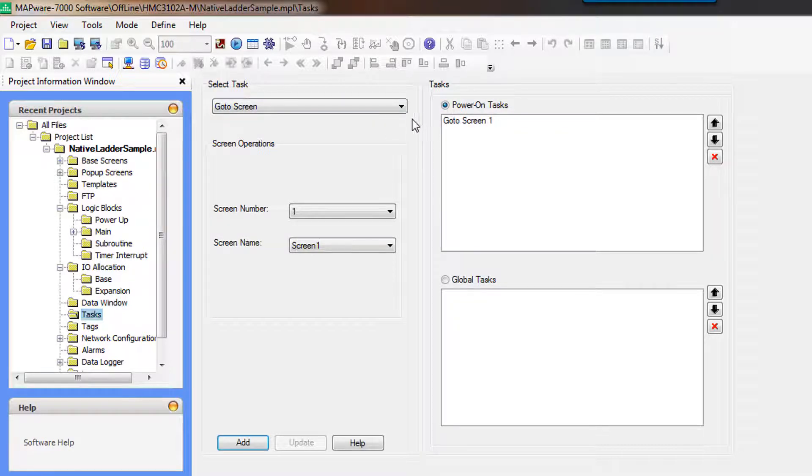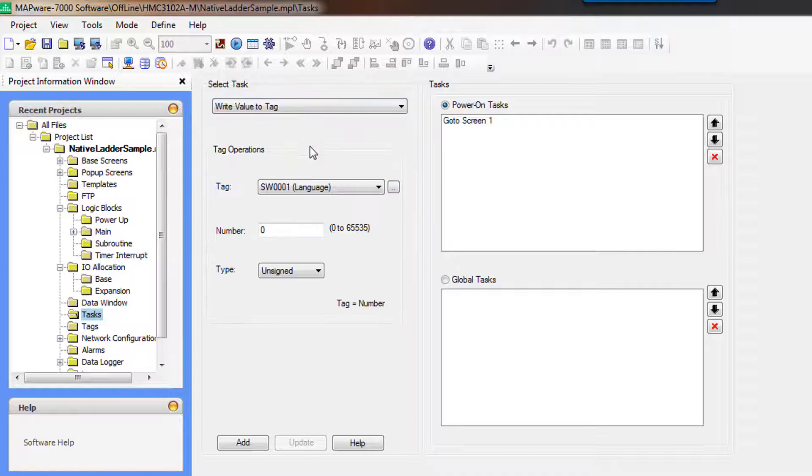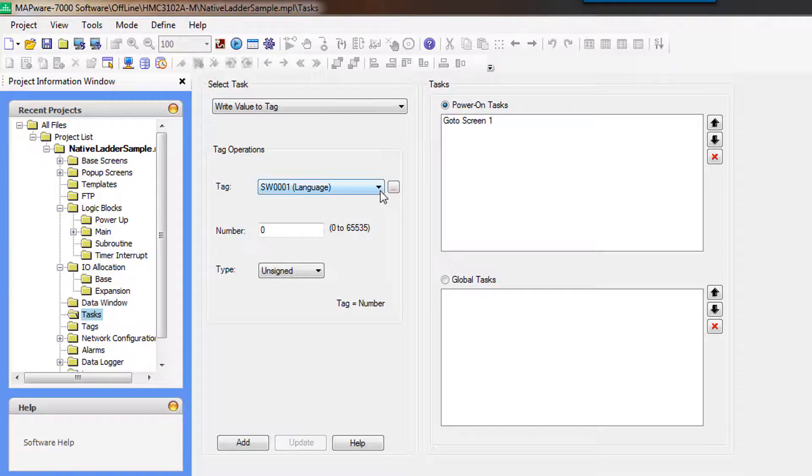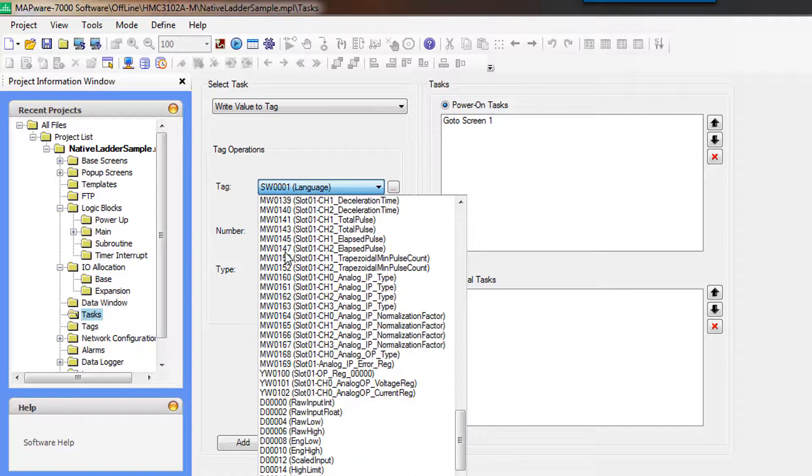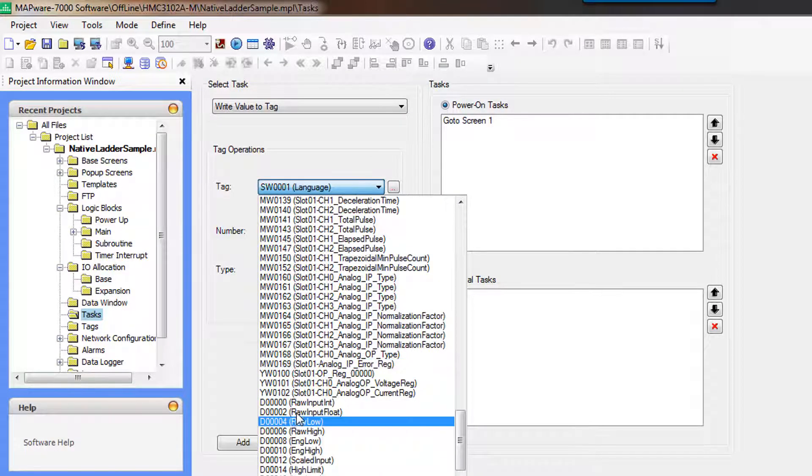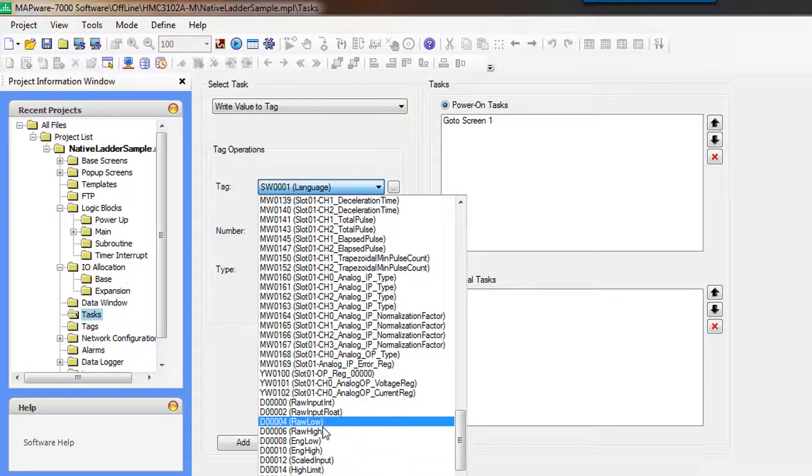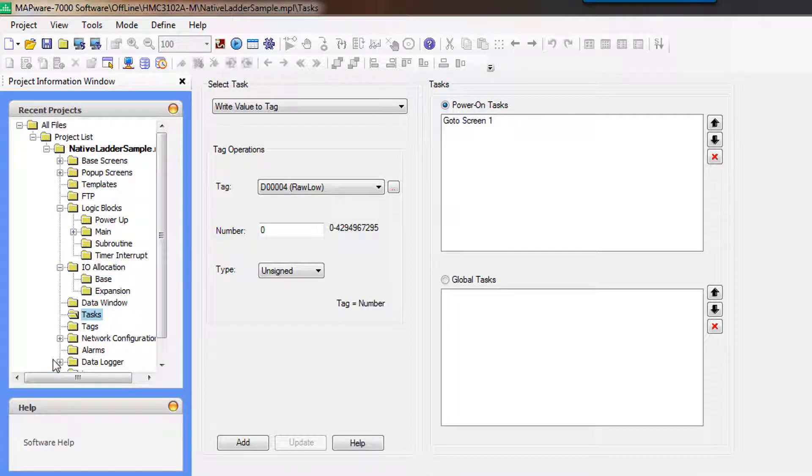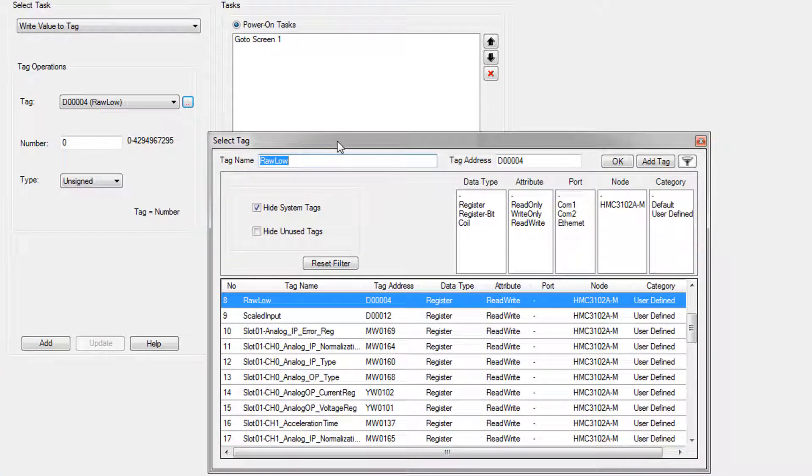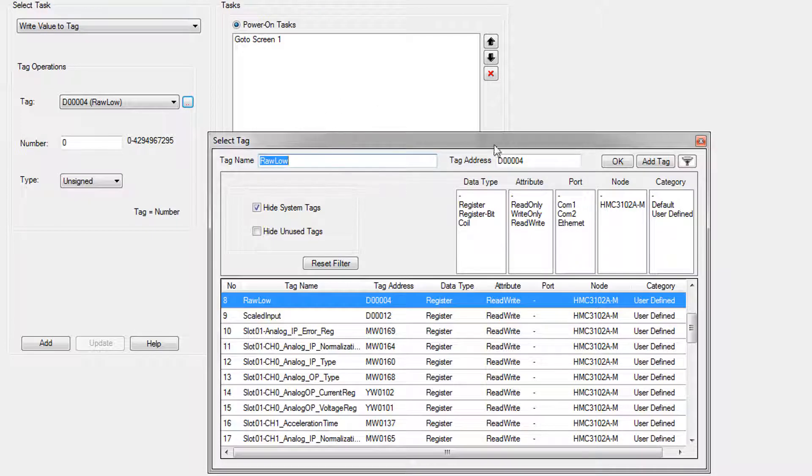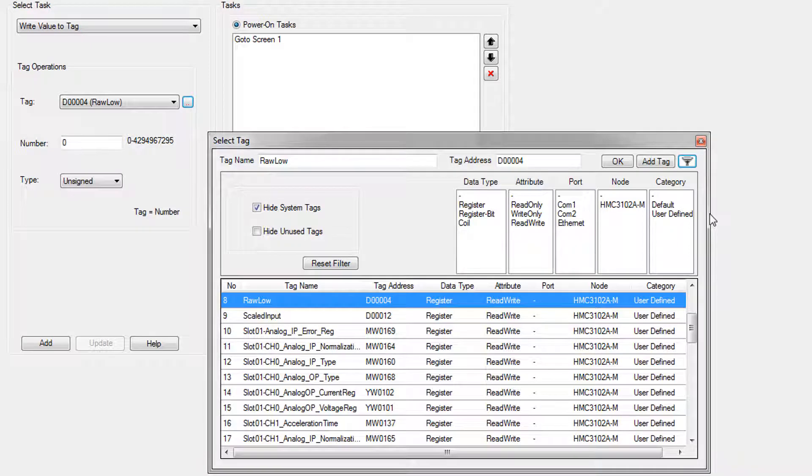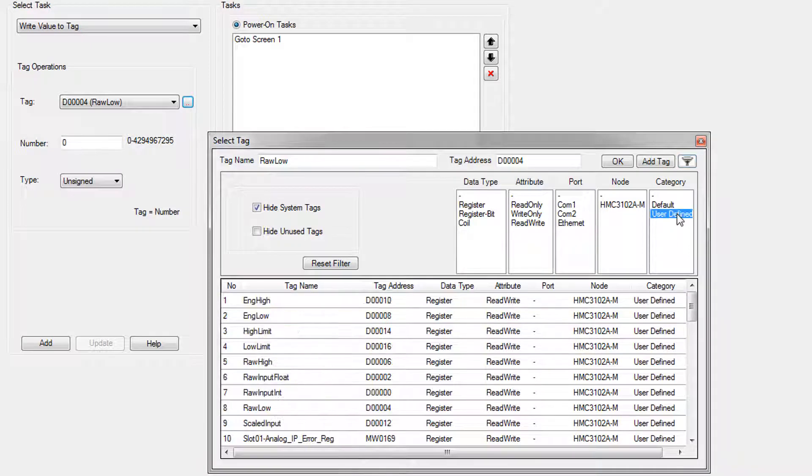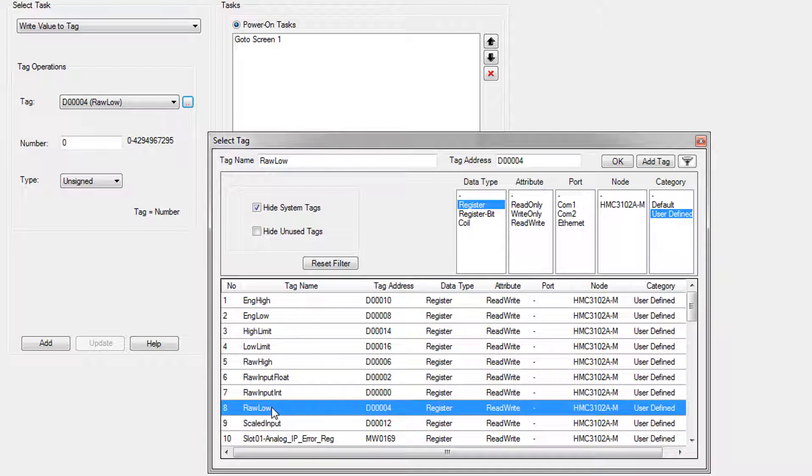So we're going to write a value to a tag. And we want to select the rawLow tag. You can scroll down to the bottom of this dropdown. Basically, as you add tags, they'll get added to the bottom because that's how it works. So we could select rawLow there. Or this ellipse button will open up the select tag dialog box. And this can be a lot more convenient because you've got your filters. So we could filter to just user defined and we only want registers.